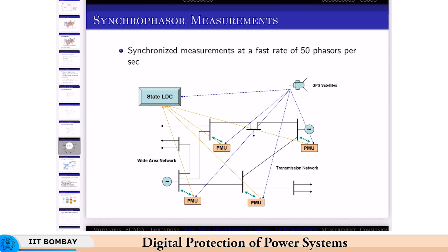So you contrast that with SCADA, which is 20 milliseconds or 40 milliseconds versus 1 second or 2 seconds of that order. So this is extremely fast, and then you can observe power swings and take control actions accordingly. So this is how the WAMS architecture looks. This is an outline of the architecture. The actual architecture will look like this.